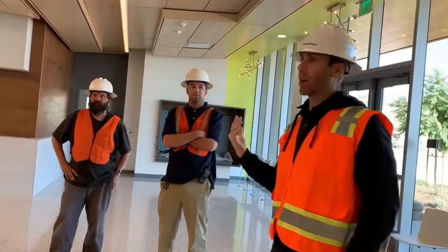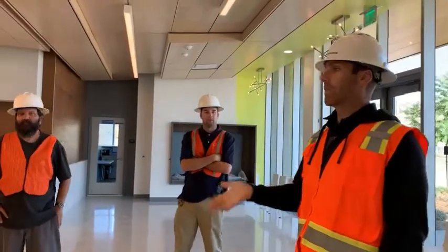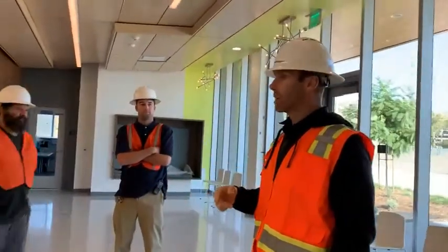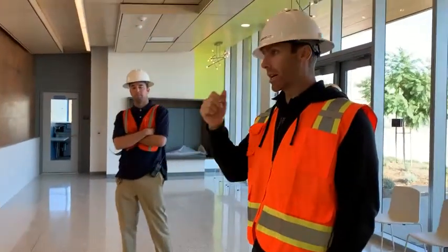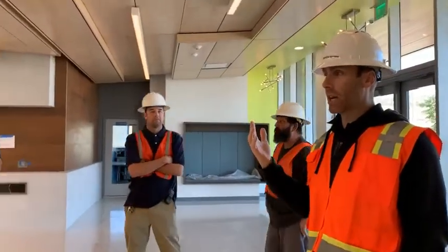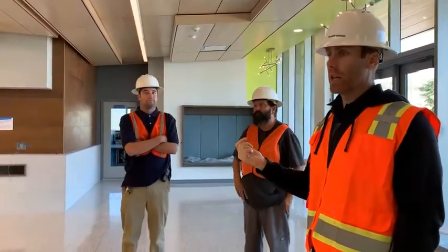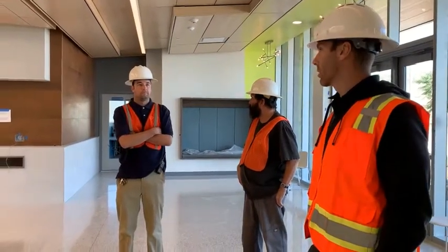Like I said, daylight harvesting is just inherent in what we program for Title 24. If you raise the lights up though, they'll stay like that until they cycle off. So for instance, they're dimmed down to 20%. If I go over the switch, raise everything up, they'll go to 100%. And until I hit off or until they turn off with the aux sensors, they'll stay at that 100%. Okay, so you kind of override it for a time.